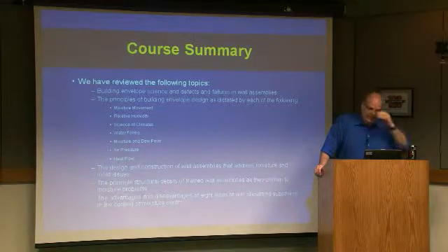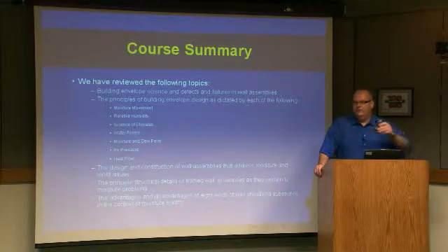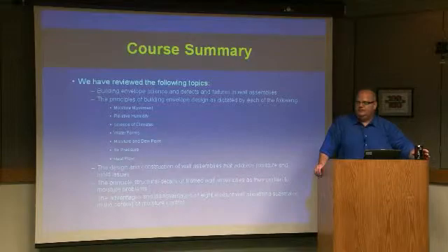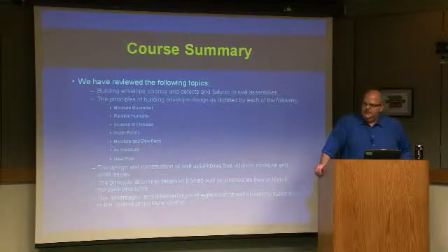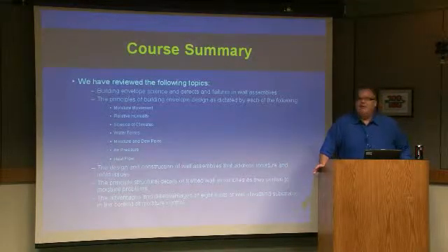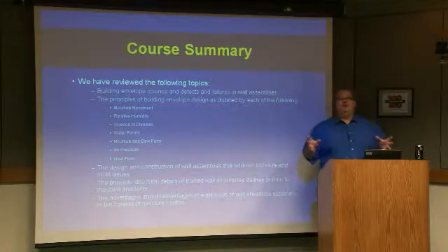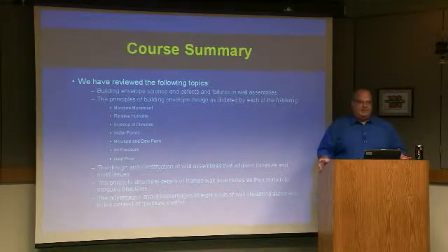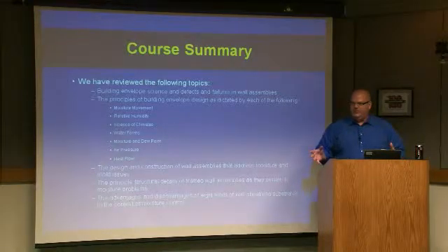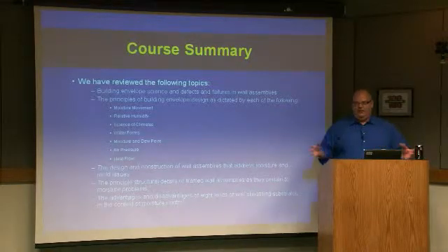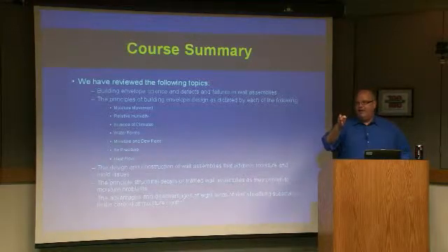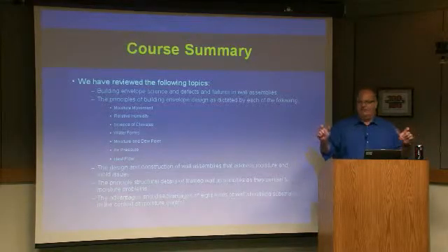I would assume if you have a kraft-faced batt, your stud facings are exposed. So at that point, I guess there could be a moisture issue. But if you put poly on top of all of that, then it covers everything. Yeah, that's a real big misunderstanding, especially among code officials. If you look at a kraft-faced batt and hold that bat, the vapor retarder is not the paper, not the kraft paper. The vapor retarder is the asphalt on the fiberglass. The asphalt only goes from side to side on the fiberglass. The stapling flange is just a piece of paper.